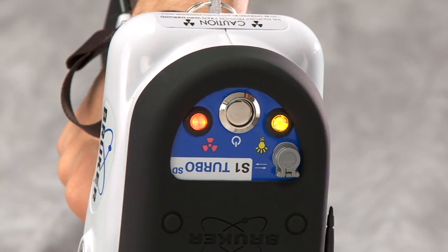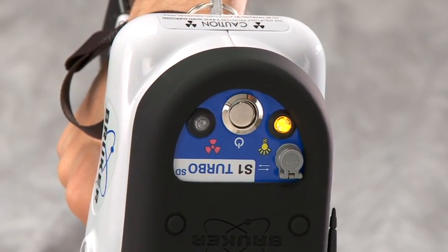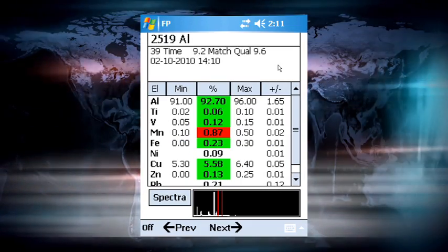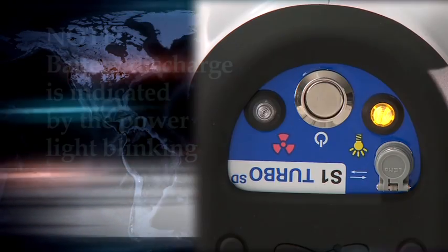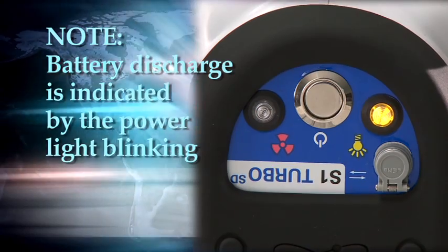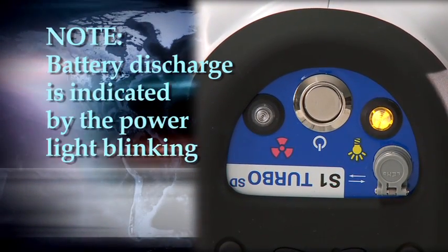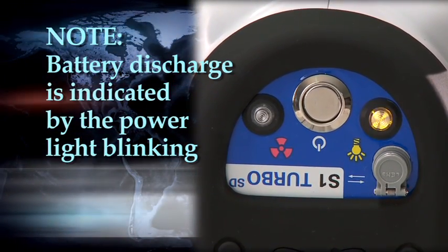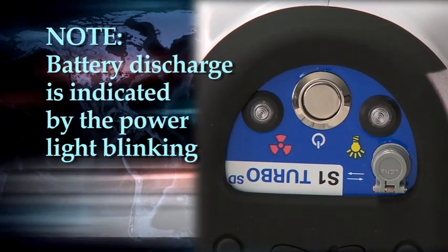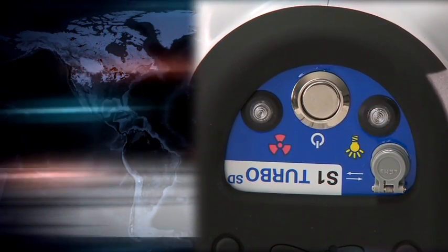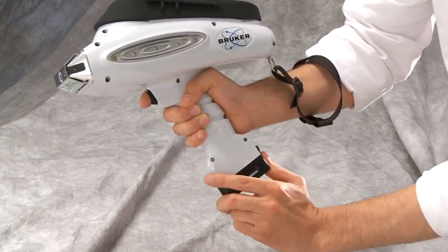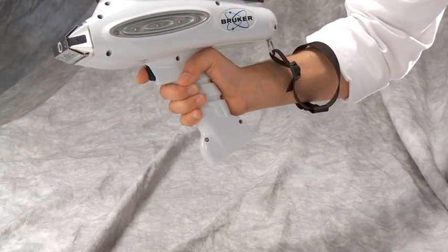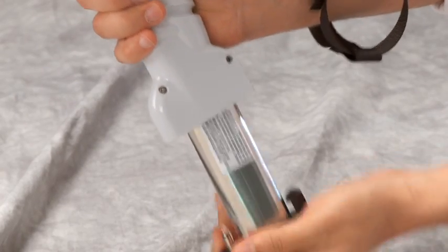If for any reason the red light goes off, the measurement will stop and no additional data will be taken. Note that one cause of premature termination of a measurement is that the battery has become discharged. At this point, the yellow light should blink, indicating that the battery charge is low. If the measurement ends prematurely, one of the first actions to take would be to replace the handle battery with a fully charged one.